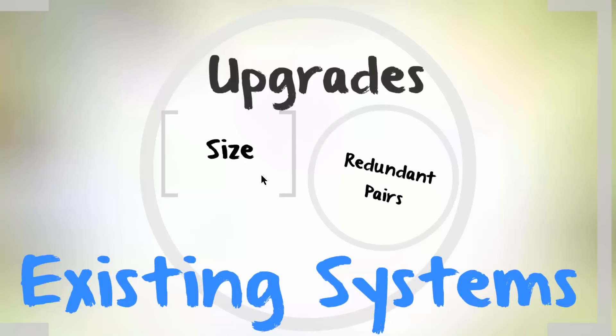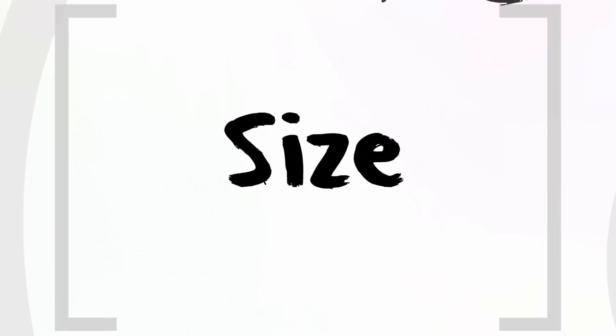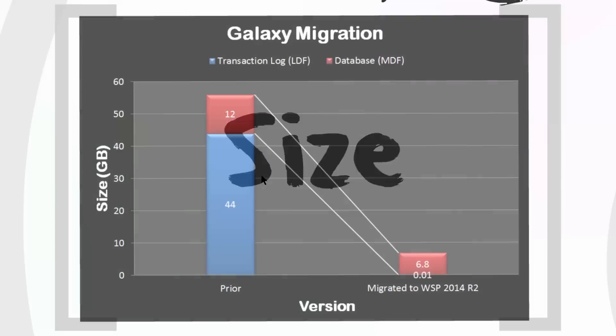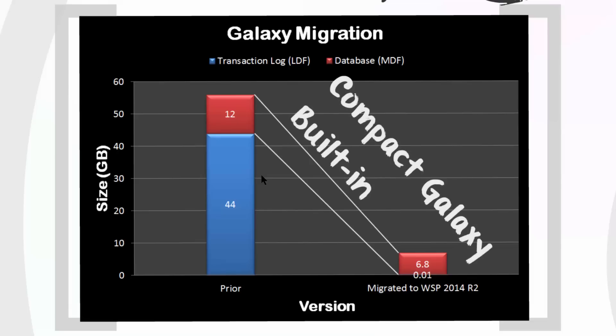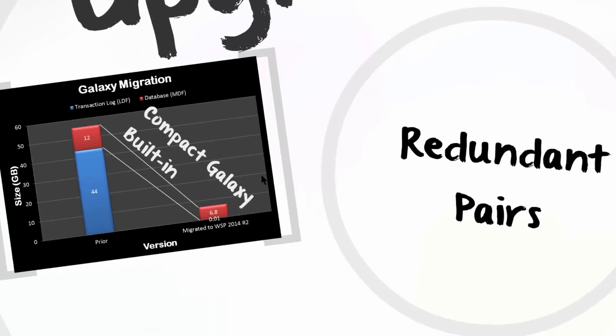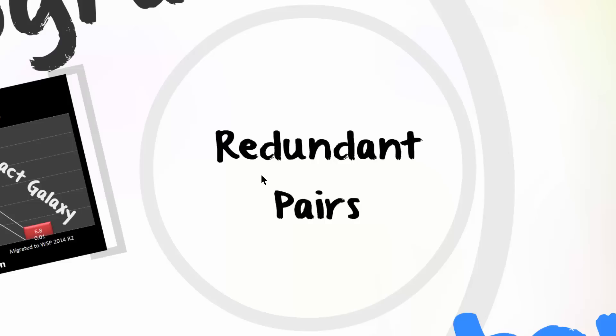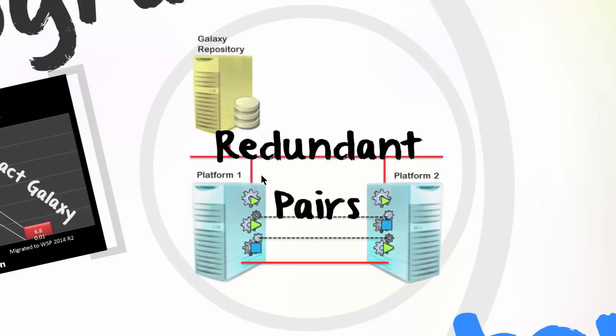Let's segue for a moment to users with existing installations. We wanted to ensure that we improved the upgrade experience. Maximizing uptime of running systems is very important to us. During the software upgrade, older versions of applications must be converted to the new version. We included a cleanup and compression process of the Galaxy application to reduce database growth that is incurred during day-to-day configuration operations. While upgrading the software, keeping the client running is very important. We have added support to redundant configurations to allow upgrading one of the pairs while keeping the existing one running, so impact to the running environment is almost completely eliminated.